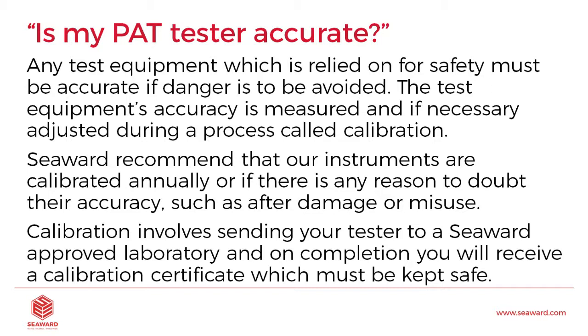So again, the calibration side there is done annually, and again is very common. But Seaward recommend that our instruments are calibrated annually, and if there's any reason to doubt their accuracy, such as after damage or misuse. Calibration involves sending your tester to a Seaward approved laboratory, and on completion you will receive a calibration certificate, which obviously must be kept in a nice safe place.